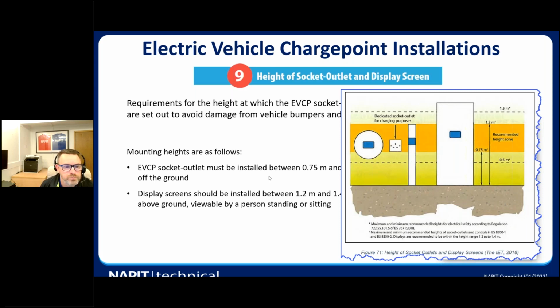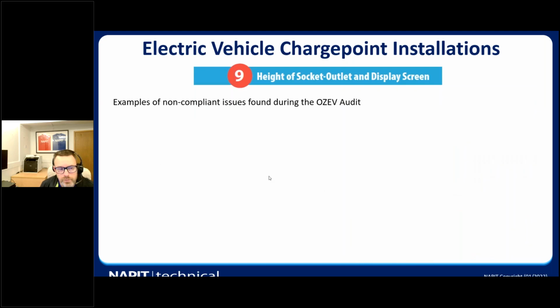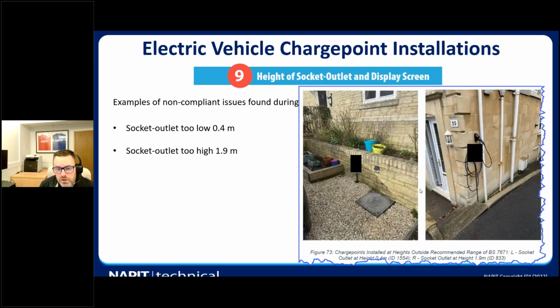So that's where we're looking at the height of the sockets and the height of the display units as well. These are some examples of the non-compliant issues that are picked up during the audits. The socket outlet is too low, 0.4 meters. Socket outlet is too high, 1.9 meters. They're blanked out, so the manufacturers of the charge points are not shown, but you can see this one's too low for access, and this other one, the socket outlet, was too high as well to access it and the display.